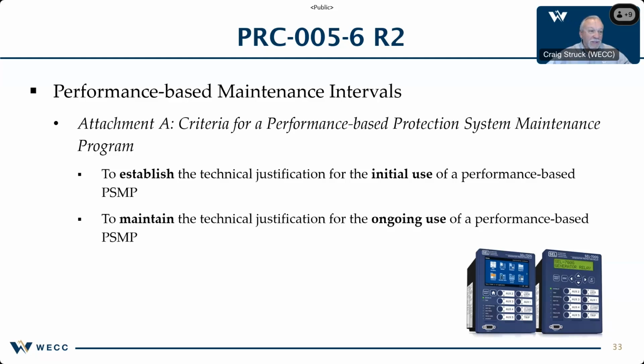Thanks, Jessica. So Jessica's covered R1, which requires the establishment of a PSMP under either the time-based or performance-based maintenance intervals, and the inclusion of all applicable components. R2 only applies to the transmission owner, generator owner, or distribution provider that chooses to establish performance-based maintenance intervals. R2 requires those entities to follow the procedure in PRC-005 Attachment A to establish and maintain justification for the initial and continued use of performance-based intervals.